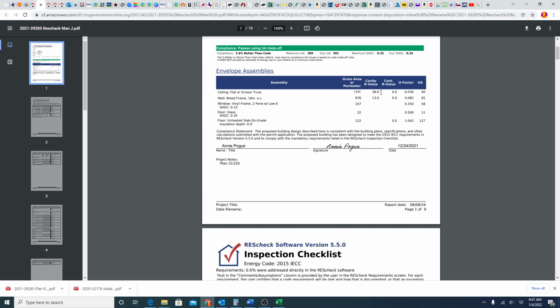Most foam insulators only let you put a certain amount of inches of foam that they can verify as an effective R value. Or they have an installation standard that limits you to X amount of inches. Closed cell foam is generally 2 to 4 inches. Open cell foam can sometimes be up to 8 inches. I've seen some applications up to 12 inches.